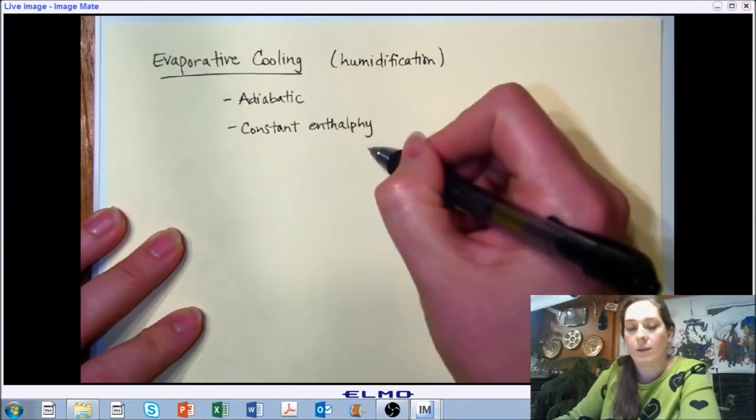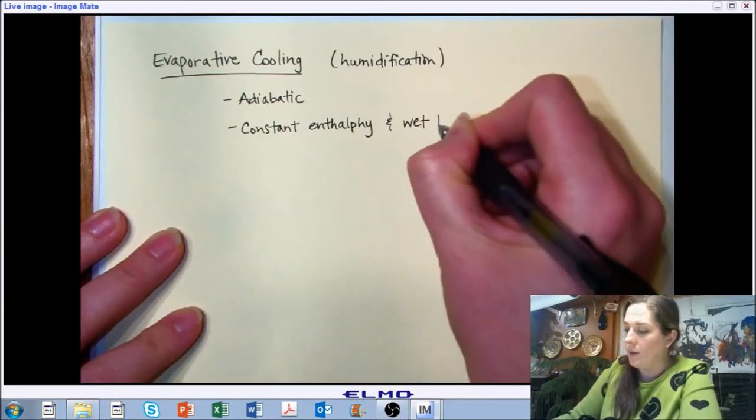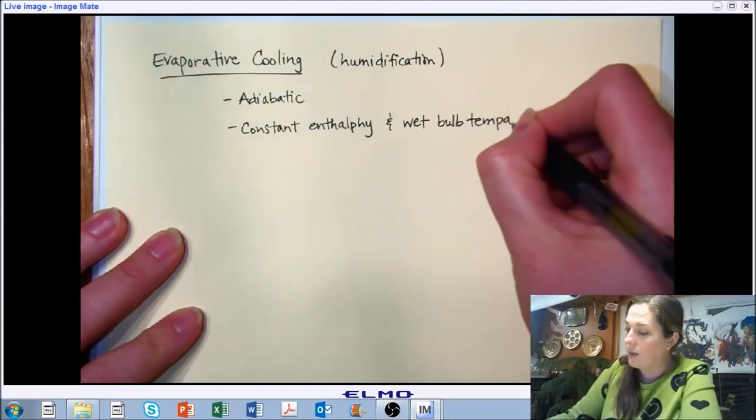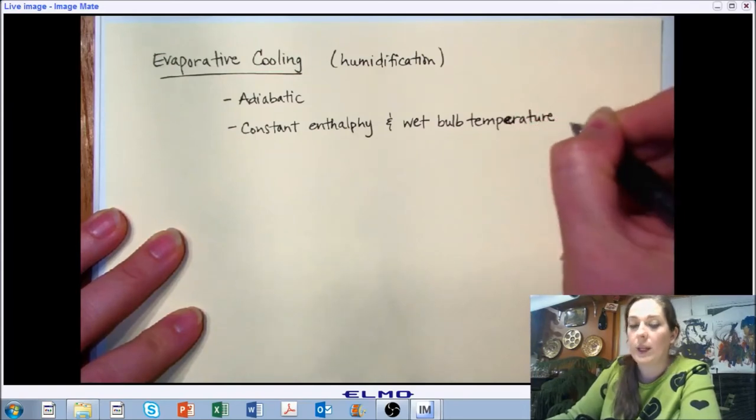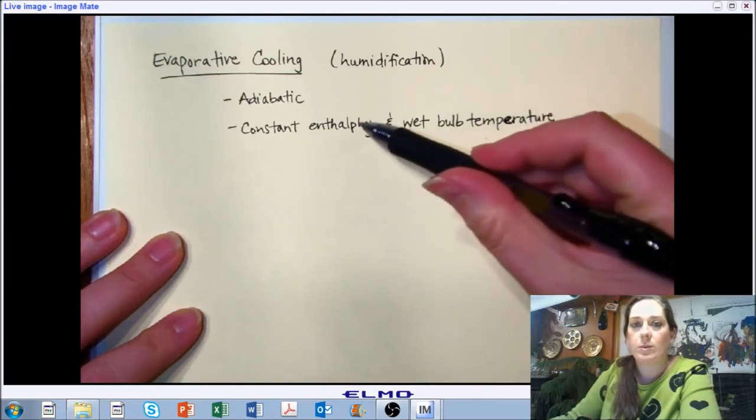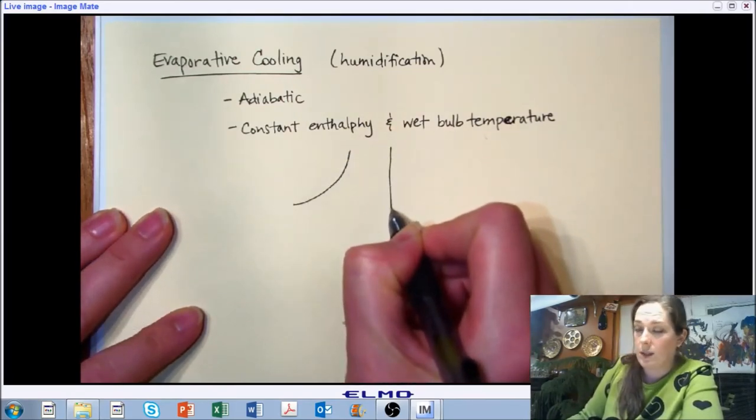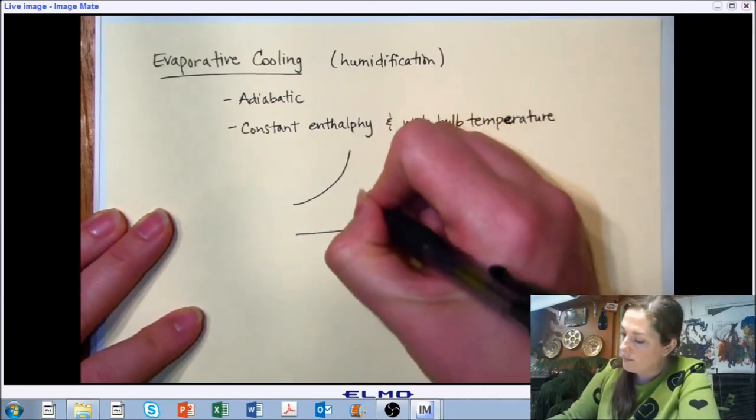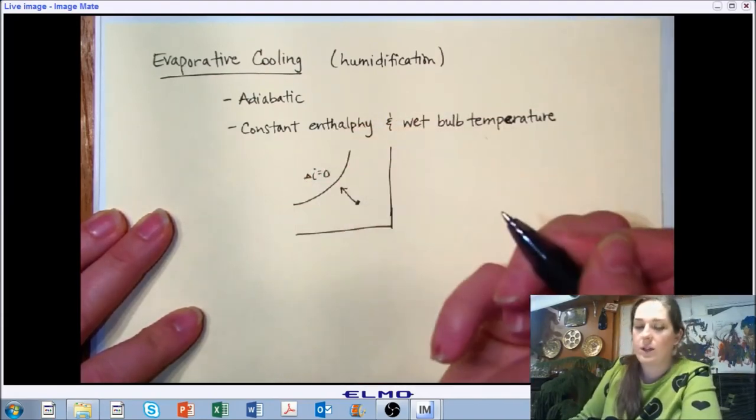In this case, we'll stay on a line of constant enthalpy. And while our wet bulb temperature and our enthalpy lines are not identical to one another, they're pretty close. And for all intents and purposes, when we do evaporative cooling, we're staying along a line of constant wet bulb temperature and a line of constant enthalpy. If you have to pick between the two, it's constant enthalpy. We don't have any change in enthalpy.